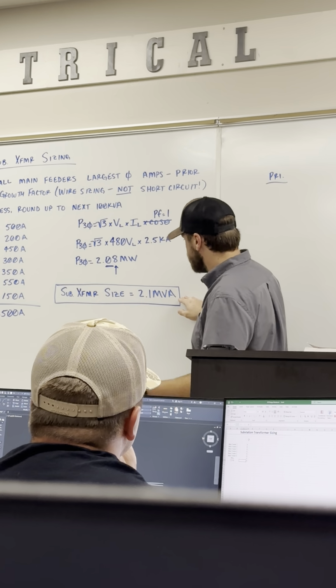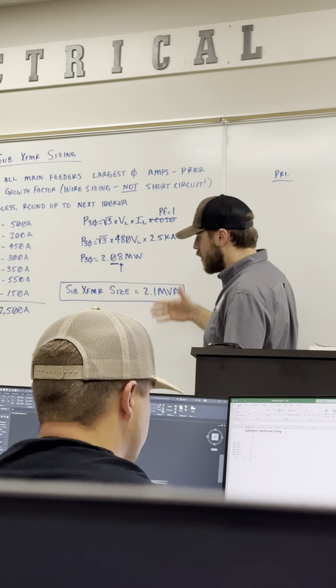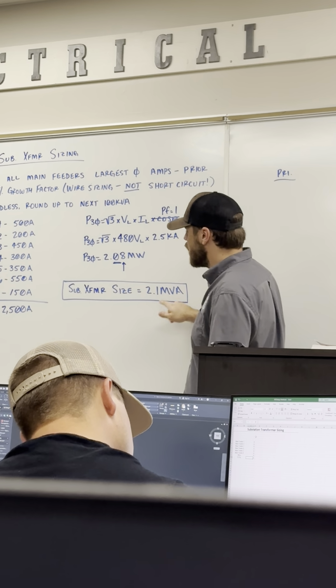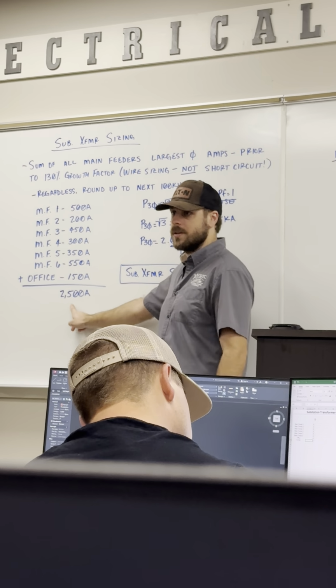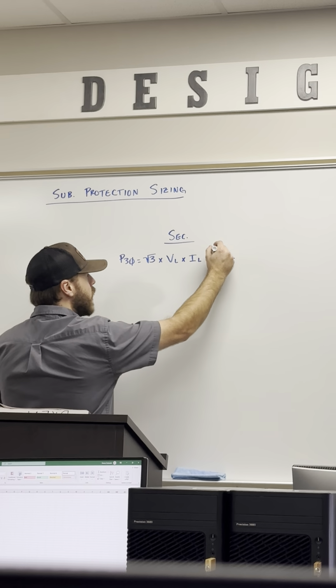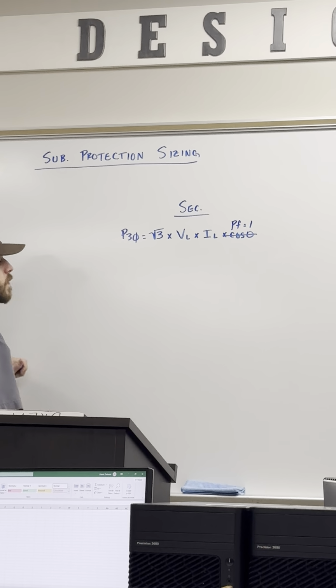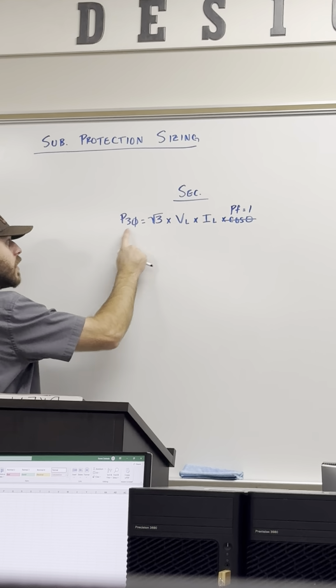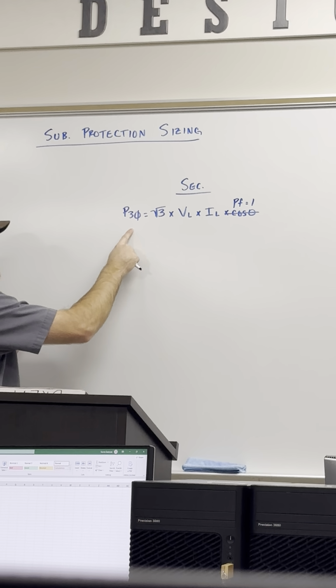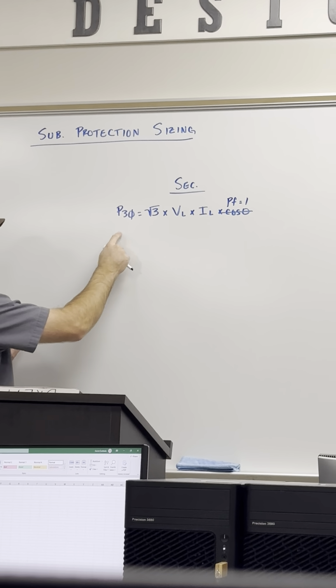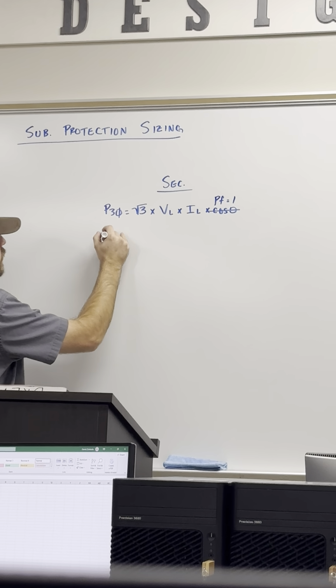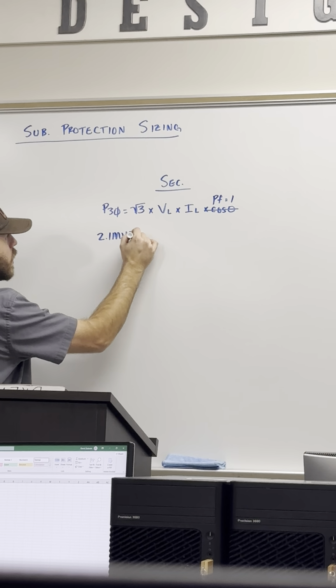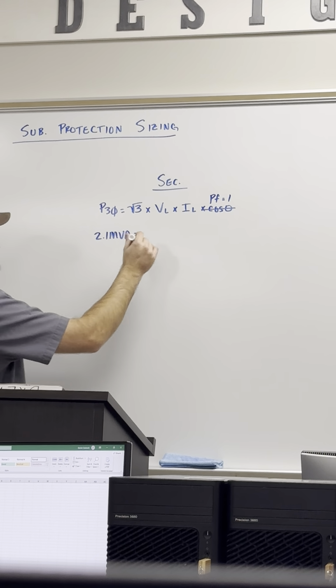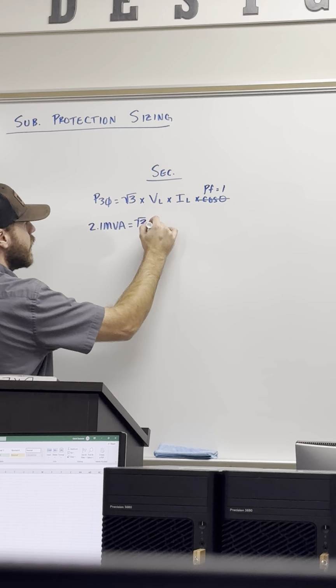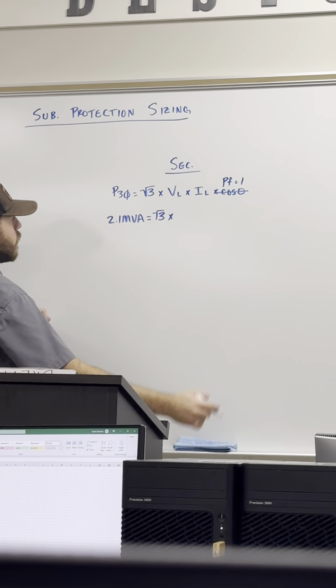In our case, or in this example, we have a 2.1. So before we even do any of the math, with this being slightly higher, I should have slightly higher amperage, right? Just ever so slightly. So, kind of going back to our conversation of this power factor being at unity, this is watts and voltamps. We know that they're the same thing. So even though this power here is dedicated for watts, I'm actually going to plug in my transformer size here. So in this case, I'm going to plug in 2.1 MVA, because voltamps and watts are the same thing, is equal to square root of 3 times our voltage on the secondary is still at 480 volts.